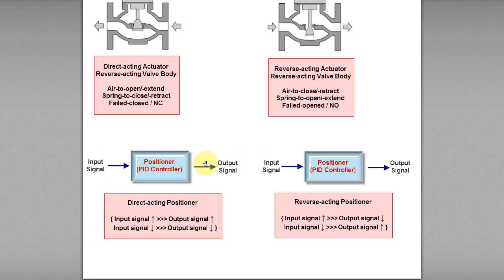As for the positioner, a direct acting positioner is one where if the input signal increases, the output signal produced by the positioner also increases, and if the input decreases, the output decreases as well. A reverse acting positioner is one where if the input signal increases, the output signal is reduced, or vice versa.